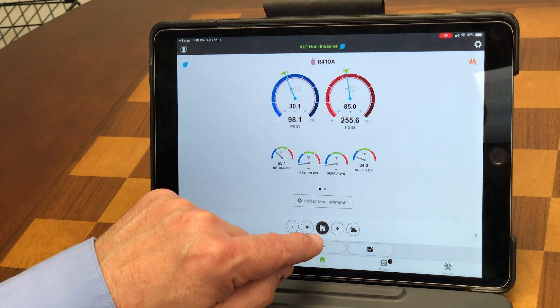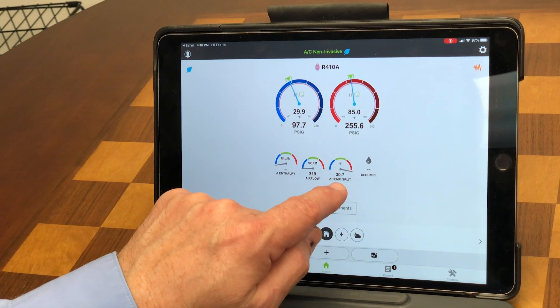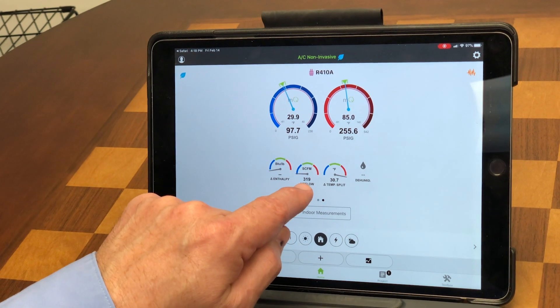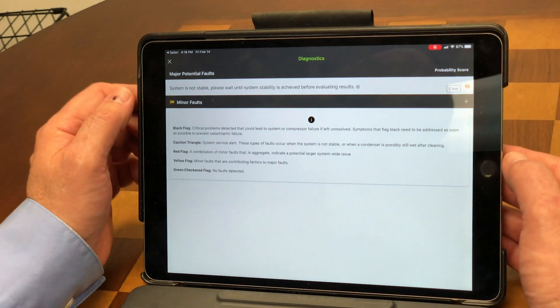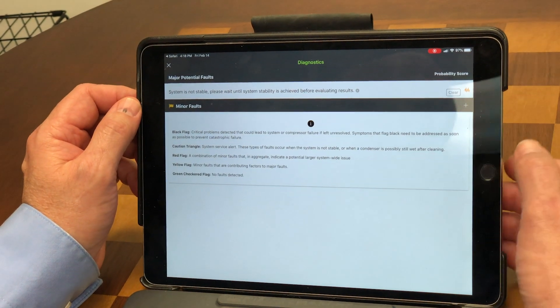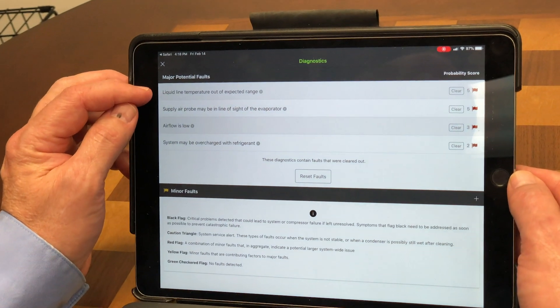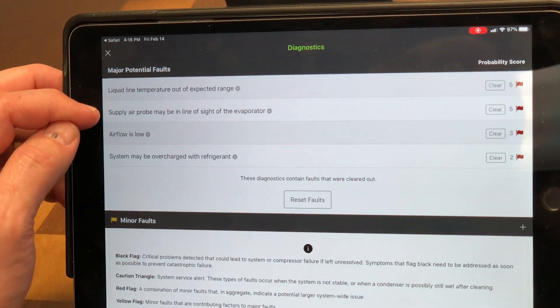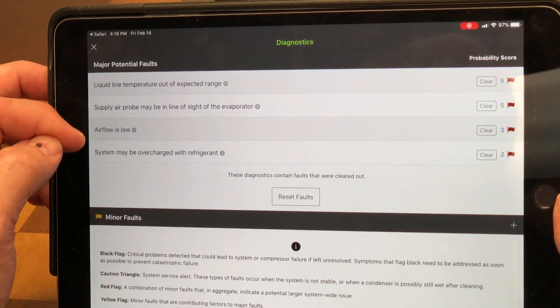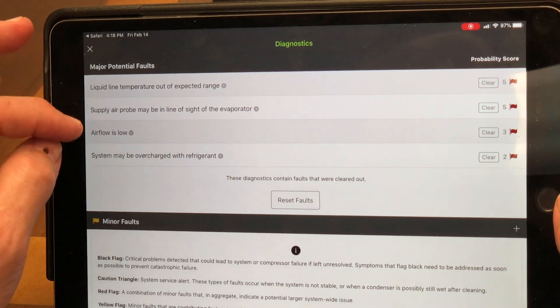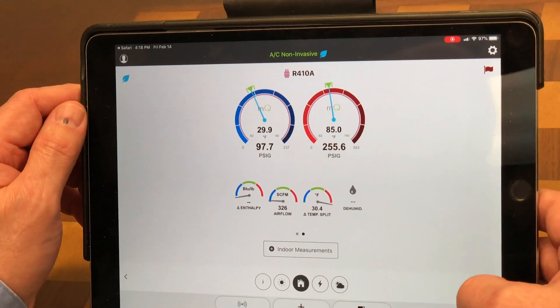This is actually using our non-invasive mode to get pressures and temperatures. I can look at my return air dry bulb, supply air dry bulb, and see my temperature split is really high at 30 degrees. Estimated airflow is really low. If I tap on this — the system is not stable yet — I can see liquid line temperatures are out of expected range, supply air probe may be in line of sight of the evaporator, airflow is low, and there could be an overcharge. They're primarily tied to low airflow on the system, very similar to what we see in Sensi Predict.